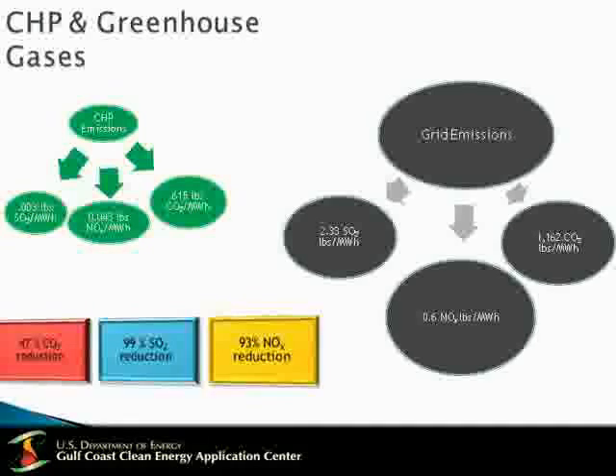Let's look at the emission signature of CHP systems. On the left, you can see the emissions from CHP systems, and on the right is the emissions from the grid. Of importance to note, there are significant reductions in all the major greenhouse gases. It's almost 1,200 pounds of carbon dioxide per megawatt hour that the grid emits. A comparable CHP system basically emits 600 pounds of carbon dioxide for each megawatt hour produced. To summarize, typically you will receive 47% carbon dioxide reduction, 99% sulfur dioxide reduction, and a 93% NOx reduction.